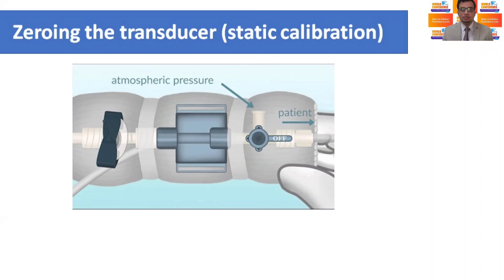For zeroing, the transducer is open to air and the recorded pressure, that is atmospheric pressure, is used by convention as 0 mm of mercury reference value.